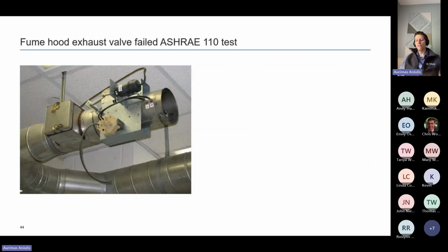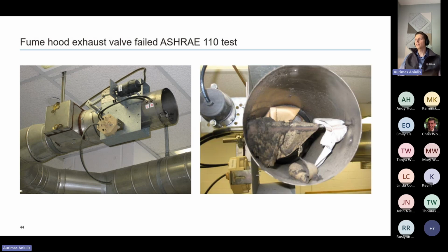Here's another example of fume hood exhaust that failed to pass the ASHRAE 110 test. I don't know what they do in fume hoods, but I wouldn't put my hands in there, especially if they're able to suck in all these tissues and whatnot to foul up the valves to that extreme. And if you've got valves that have sensors in the airstream, that's going to present another challenge.